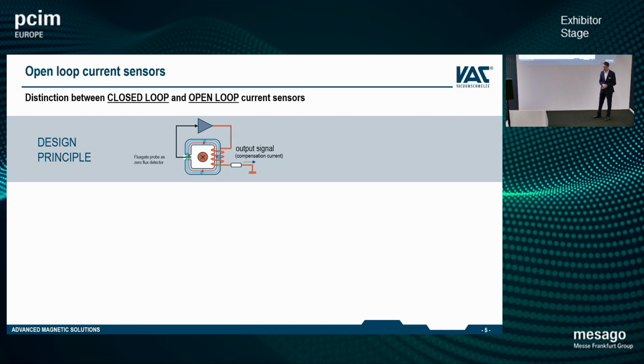If we take a look at the closed-loop sensor, you see here that we have a kind of feedback loop in the sensor. The idea is that in the sensor, we have an additional coil that drives a compensating current that will compensate the magnetic flux that is generated by the primary conductor, so the signal that we want to measure. This will be compensated by this compensating current, and accordingly, the magnetic flux in the magnetic core will be driven to zero. In the air gap that you see, we have a magnetic flux gate probe that is detecting the state of zero magnetic flux in this air gap. Once that the magnetic flux is zero, then the compensating current is giving the output signal and tells you what primary current is flowing at the moment. This is the principle of a closed-loop sensor.